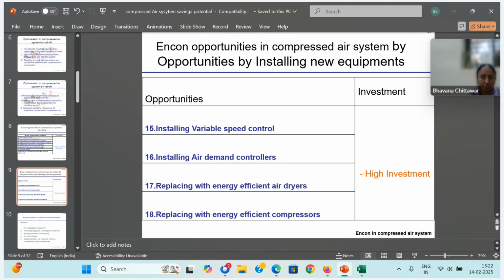Dryers should be designed properly for the operating pressure, not for the highest pressure of the compressor. It is vice versa. The compressor or receiver can be designed for high pressure, but the dryer should be designed for low pressure operation because pressure drop plays a vital role in the compressor system. If the dryer is designed for 9 kg pressure, and you are operating at 7 kg pressure, you will end up with a high pressure drop, and you lose some energy permanently. So suppliers don't concentrate on this. Actually, I mean clients have to study.